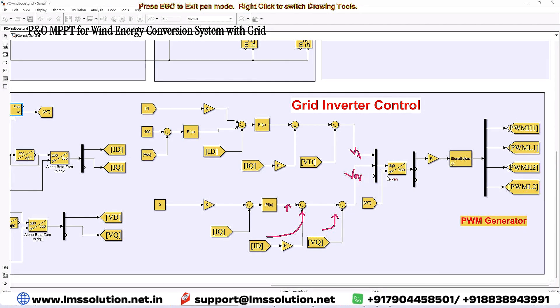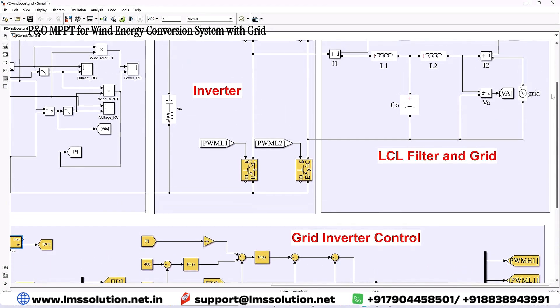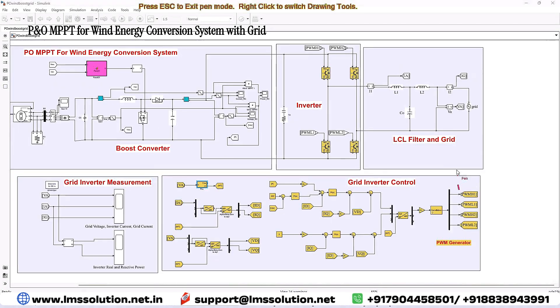The Vd and Vq references are converted back into alpha-beta form. Only the alpha component is taken and processed via a PWM generator, which generates the switching pulses for the grid-side inverter. These pulses control the grid inverter for injecting power from the wind energy conversion system into the grid.